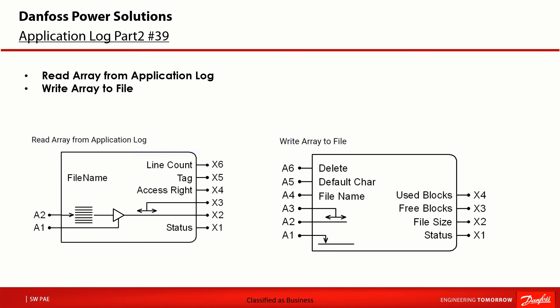The write array to file block is available only for newer controllers like the DM 10 and 1200, for example. If this block or component does not show up inside your component group 'array', it is because the HWD of the selected device does not support this function. This block gives you the possibility to write any array to an external file on the USB memory stick. You can set the position of the first byte of data to be written to the external file, the name of the file, delete the file, or append new data to existing data, as well as the array of values and the number of elements in the array to write to the file. Together with the read array from application log component, you can easily read data from the application log, build your user-defined array of values, and store these in an external file.